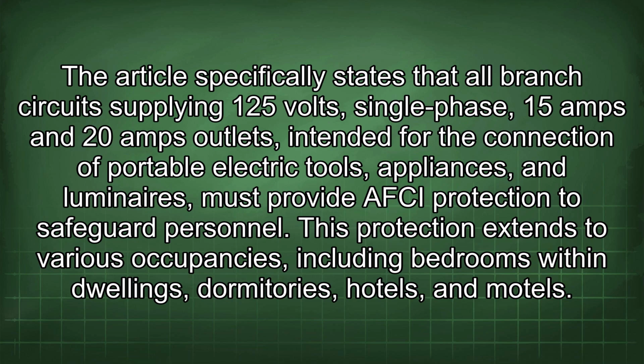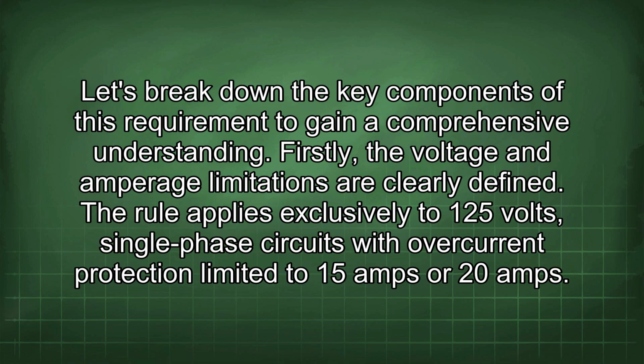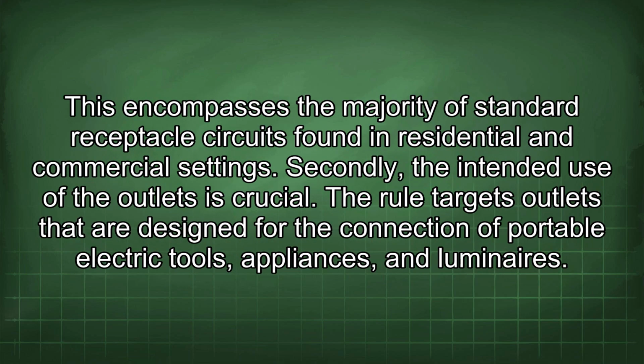This protection extends to various occupancies, including bedrooms within dwellings, dormitories, hotels, and motels. Let's break down the key components of this requirement to gain a comprehensive understanding. Firstly, the voltage and amperage limitations are clearly defined. The rule applies exclusively to 125 volts, single-phase circuits with overcurrent protection limited to 15 amps or 20 amps. This encompasses the majority of standard receptacle circuits found in residential and commercial settings.